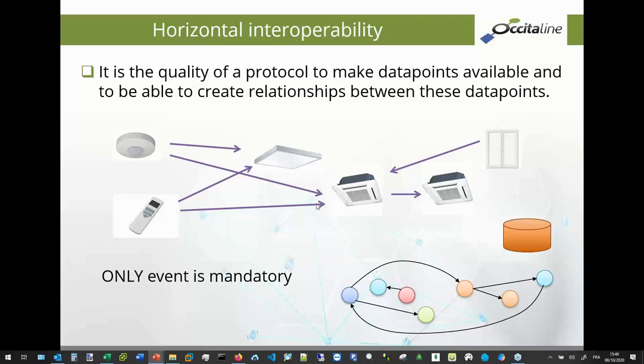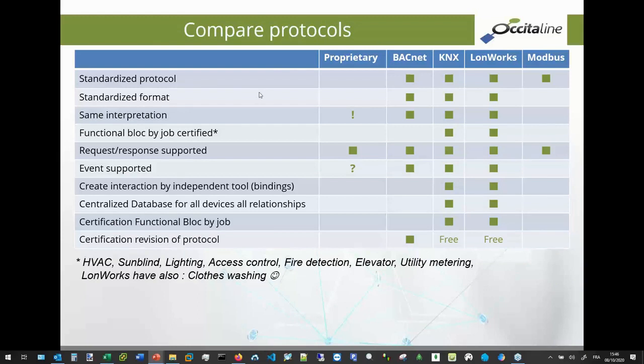When a person is detected, it is sent to the light and to the HVAC. It's the same with a remote control. When you press the push button, you ask for the light and the comfort in the room. For creating that, we probably also need a database for giving a logical address to each device and creating each connection, binding in LON, but we are not only working in LON. We need to create this connection with this link, and apply to this link some properties, some services described just after for security, and we will speak about that.